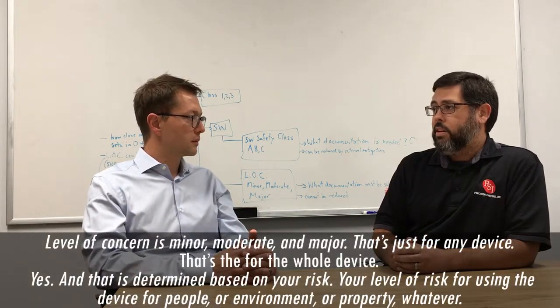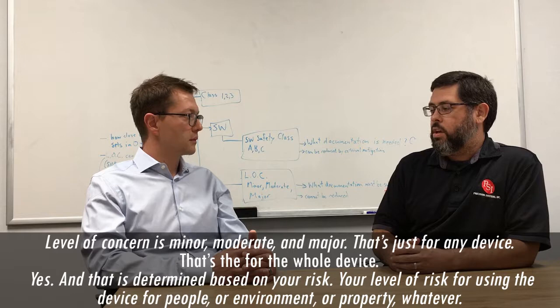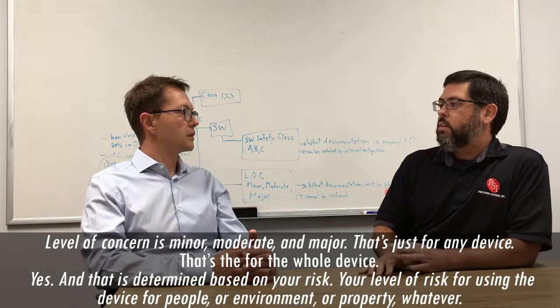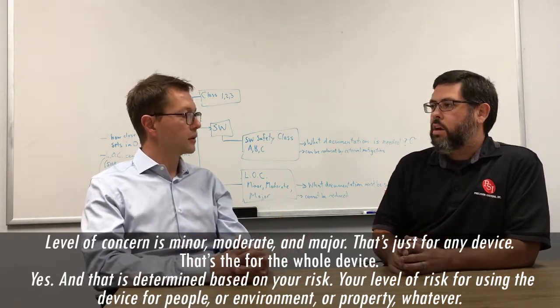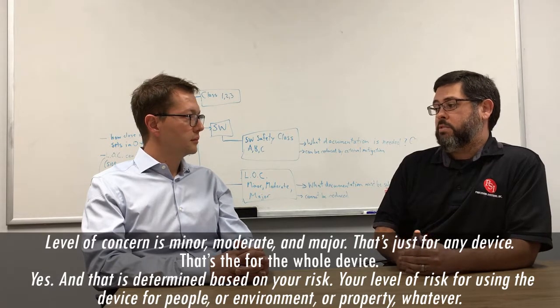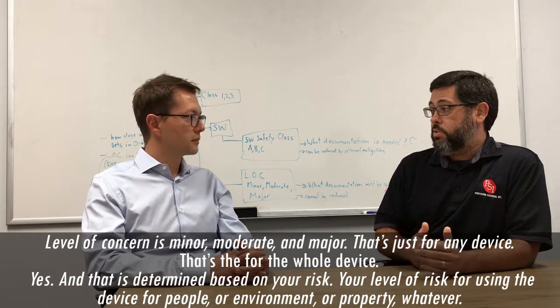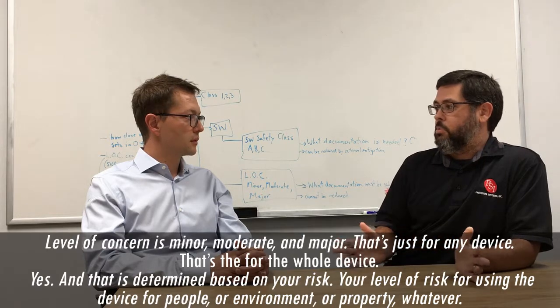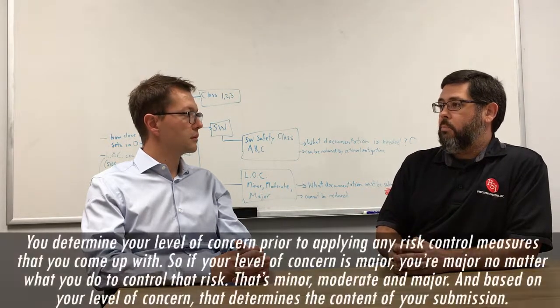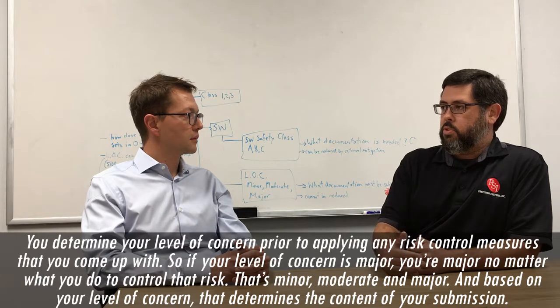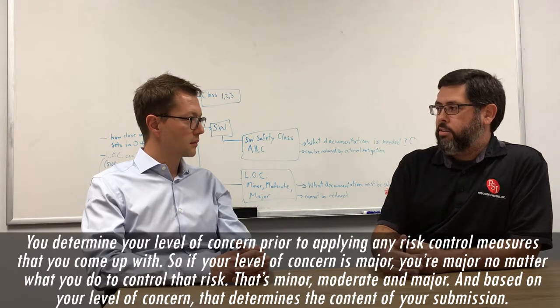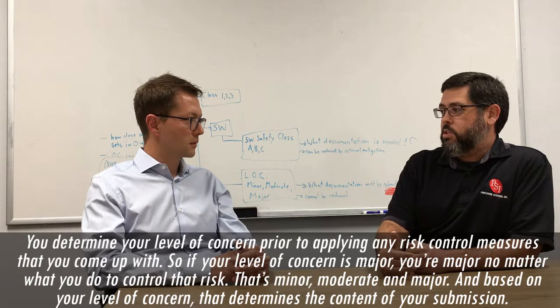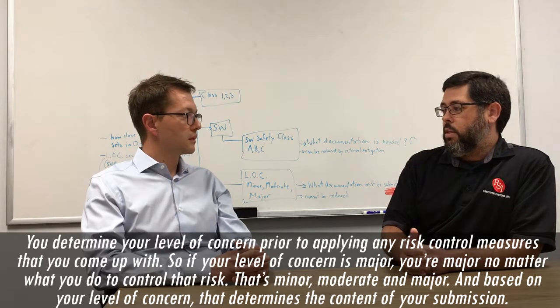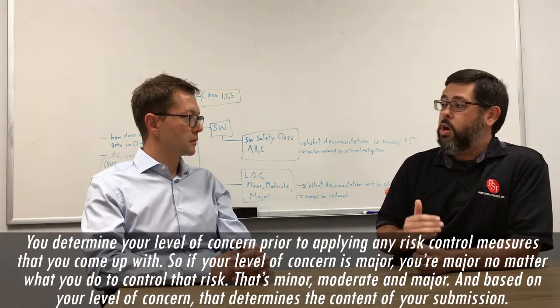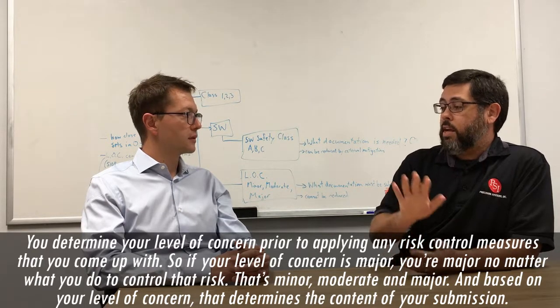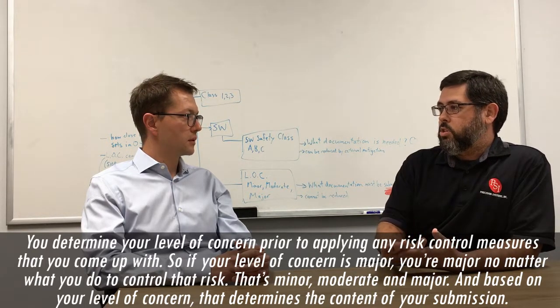Level of concern is minor, moderate, and major. And that's just for any device, for the whole device. And that is determined based on your risk, the level of risk for using the device to people or environment or property or whatever. And you determine your level of concern prior to applying any risk control measures that you come up with. So if your level of concern is major, you're major no matter what you do to control that risk. That's minor, moderate, and major.